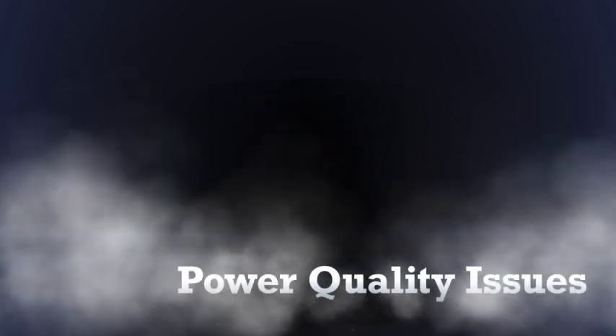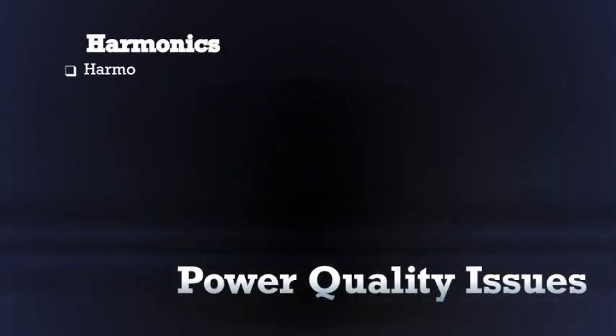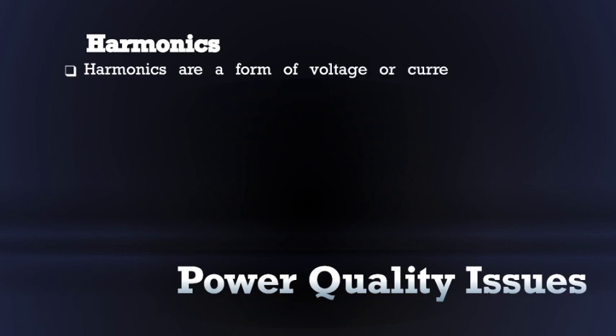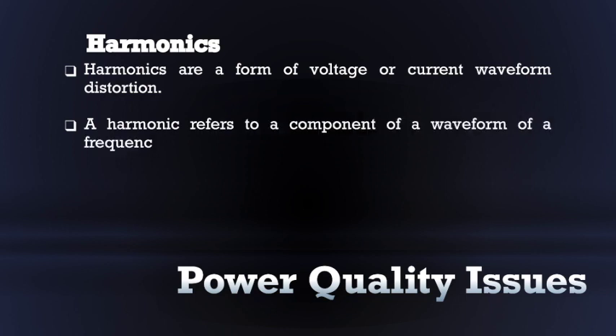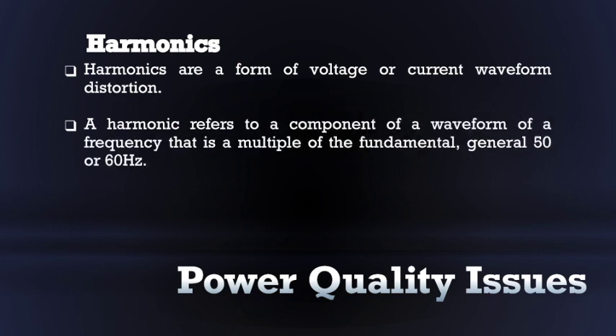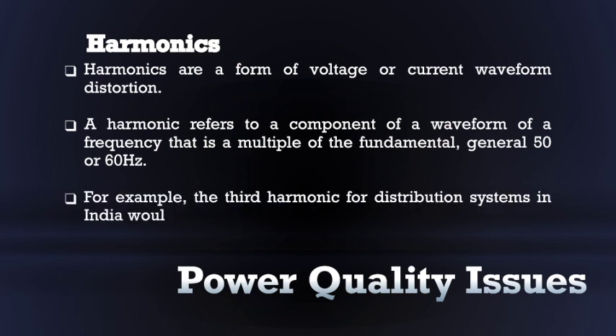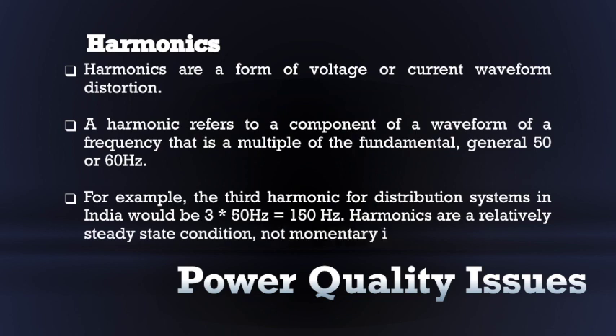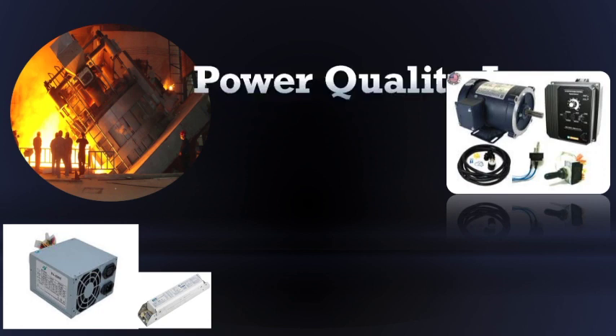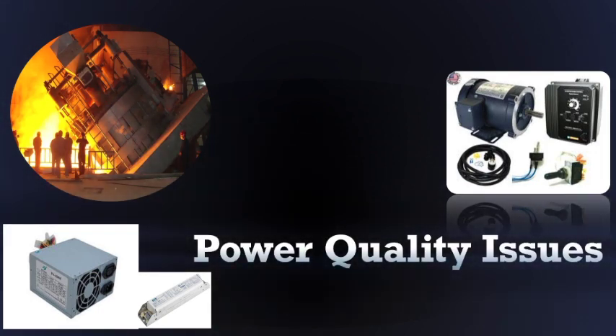Now we will discuss about harmonics. Harmonics are a form of voltage or current waveform distortion. A harmonic refers to a component of a waveform of a frequency that is multiple of the fundamental, generally 50 or 60 Hz. In India, our power frequency is 50 Hz. So, the third harmonic for distribution systems in India would be 3 into 50 Hz, which is equal to 150 Hz. Harmonics are a relatively steady state condition, not momentary in nature.